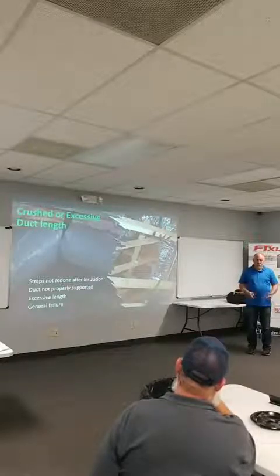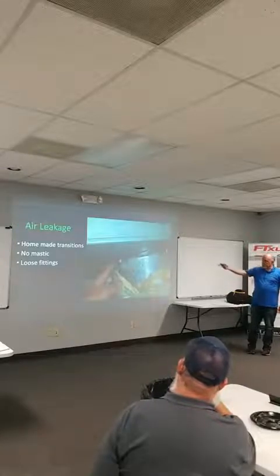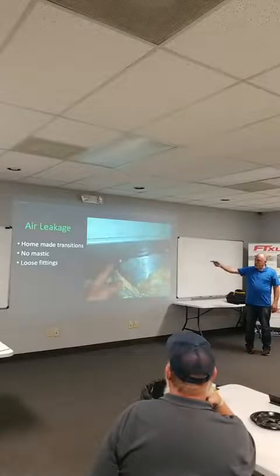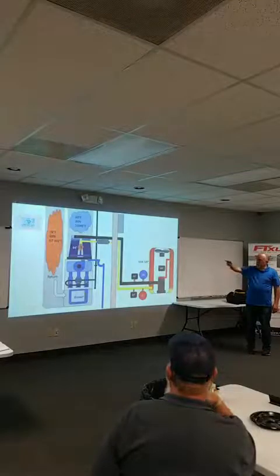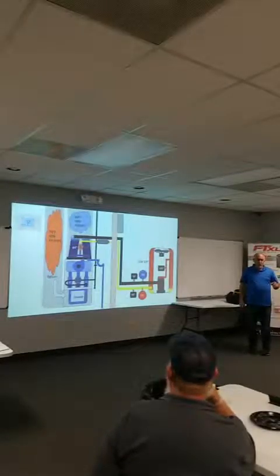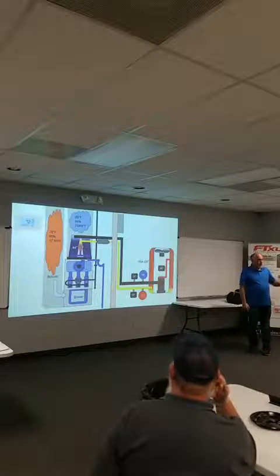So they're losing all the cooling that they had in this house into the duct system, right? Pull and sit down, you see the homemade transitions, no mastic, right? This is a telltale. When you walk into this space, I always used to make a mental note.